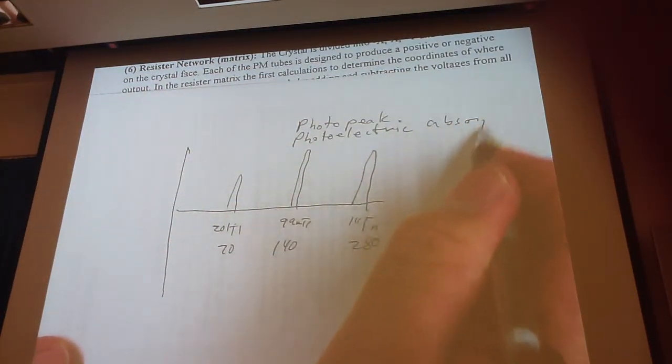Okay? So when you change radionuclide setting, this is what's actually happening now: we're either increasing or decreasing the amplification until that peak is under the window. Okay.